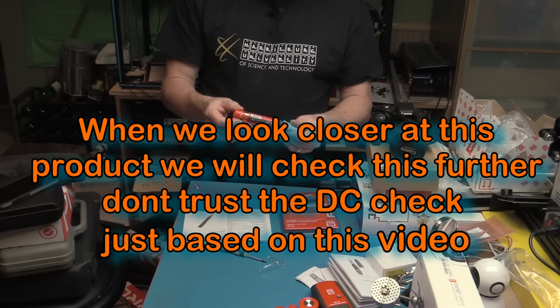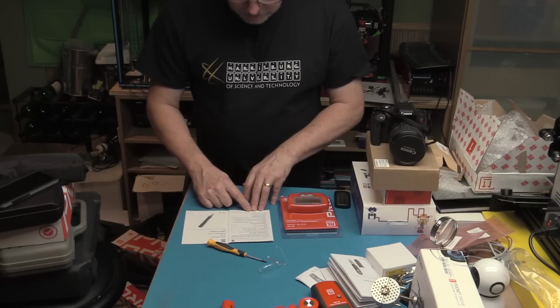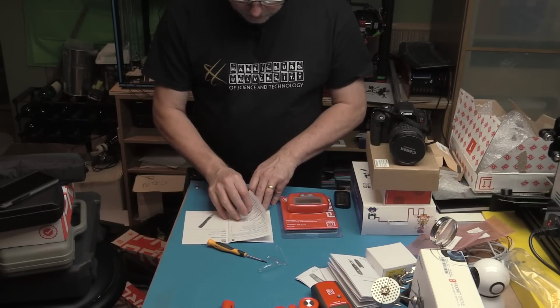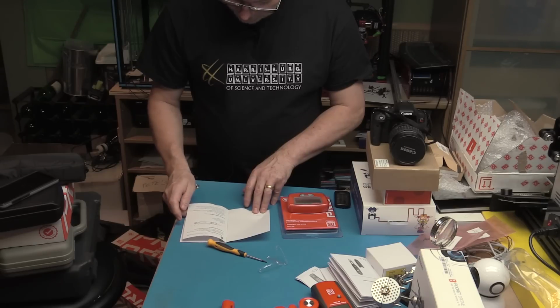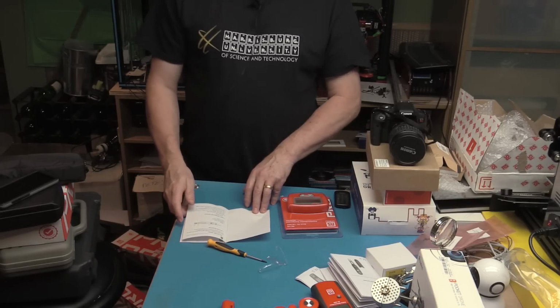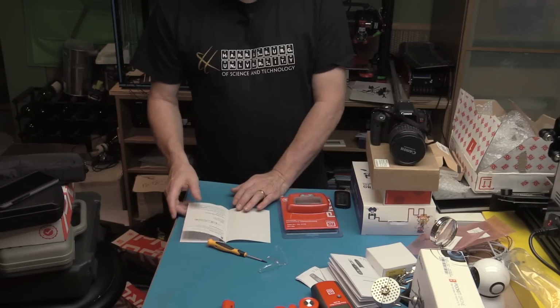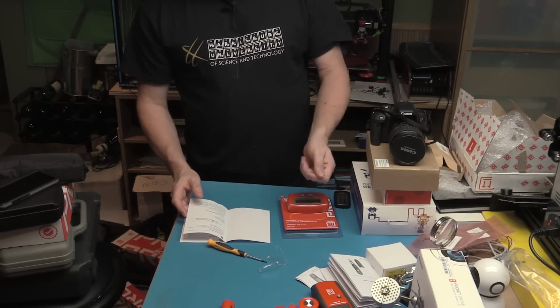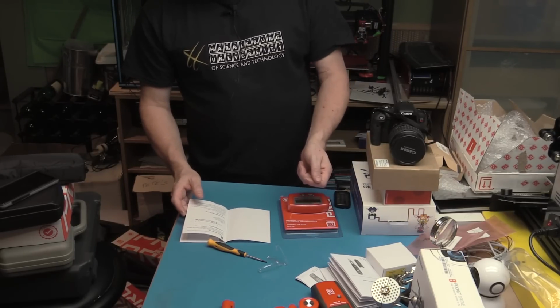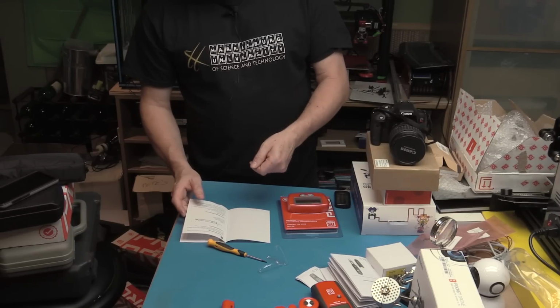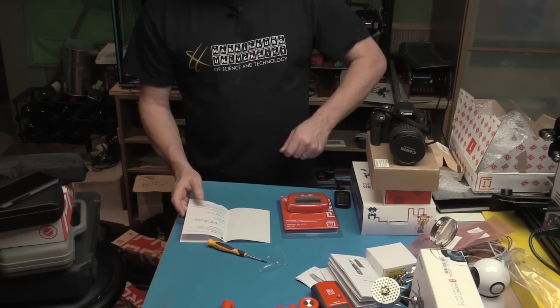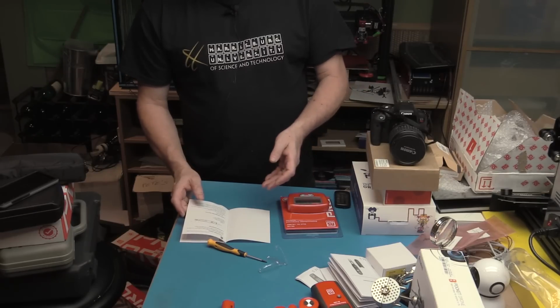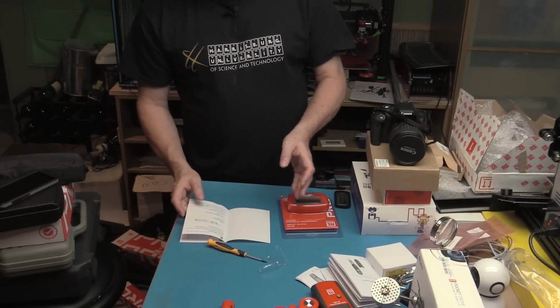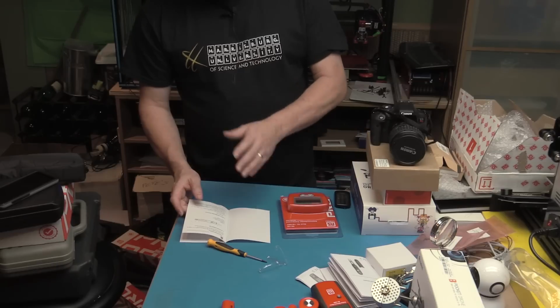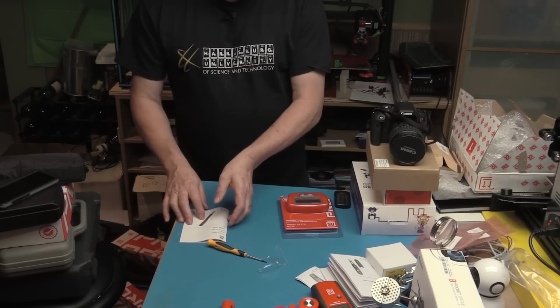Probably when you're not testing something, it has a very, very low leakage. Doesn't say how long the battery would last, but I'd imagine it would be quite a long time. That's also one of the reasons why with battery equipment like multimeters, you want to test on something you know will trigger it, then test what you're really interested in, and then go back and test again, because a flat battery means you'll get no indication. That doesn't mean it's safe, it just means you don't know. So test it first, then go on, and then test it again.